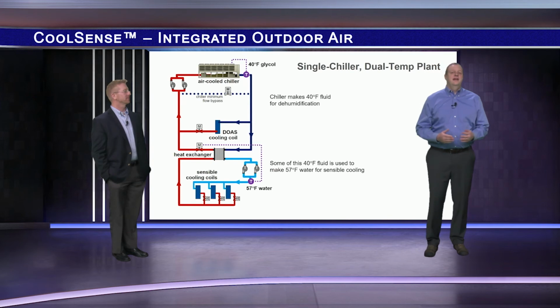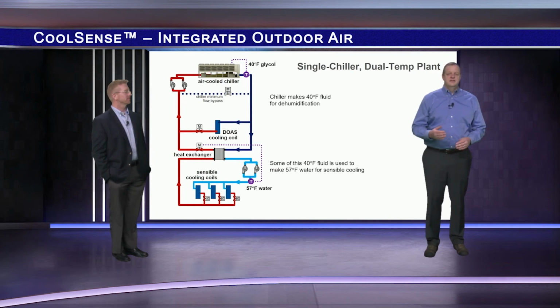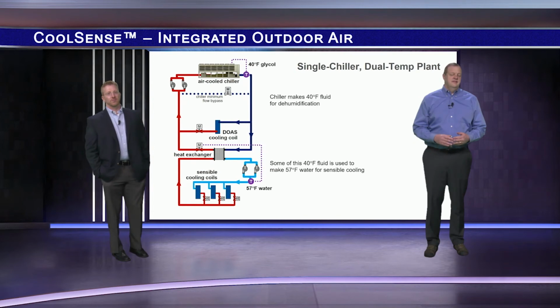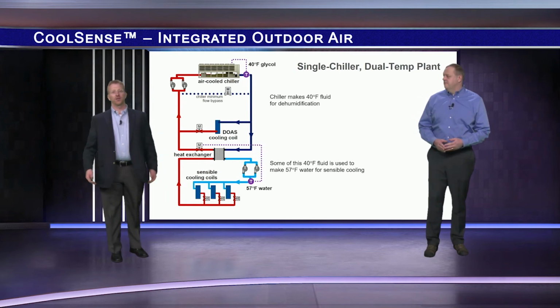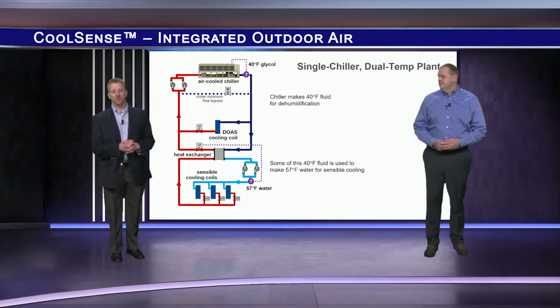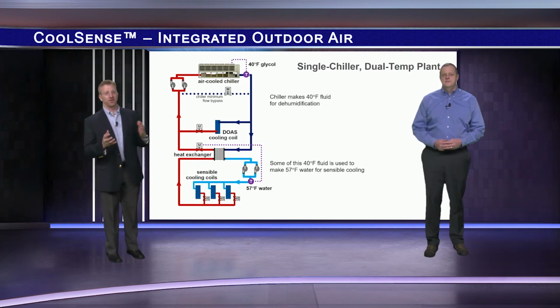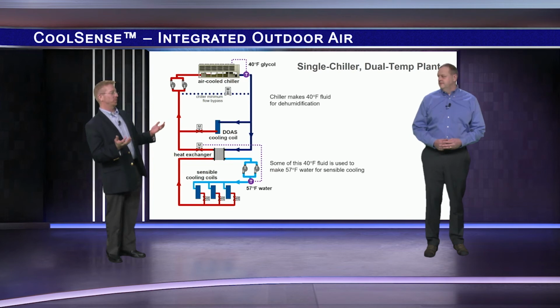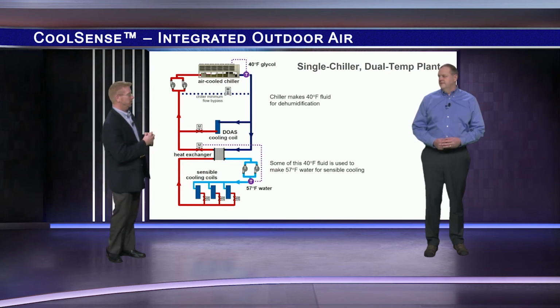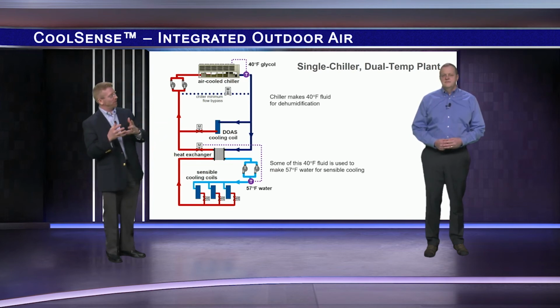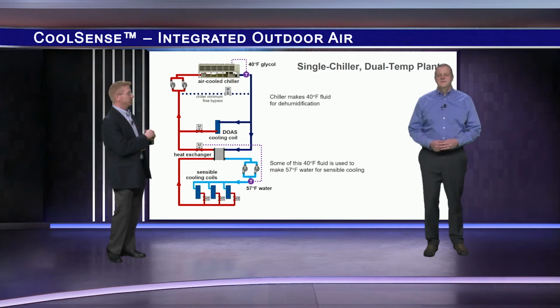Now there are certainly other plant configurations possible, single or multiple chillers, air-cooled or water-cooled, and each has its own advantages and drawbacks. Even though there's lots to talk about, we just don't have the time in this length of video. John, as you point out, it's notable how simple the CoolSense chiller system can be, but ice is just too good a match for CoolSense to not at least show the viewers one more chiller configuration, one that uses ice to make 40-degree fluid and the chiller to make the warmer water temperature.